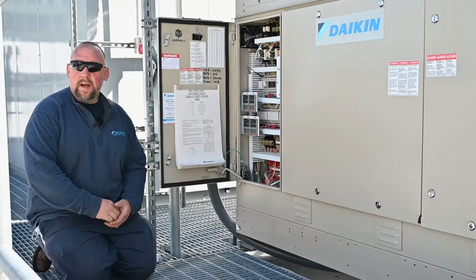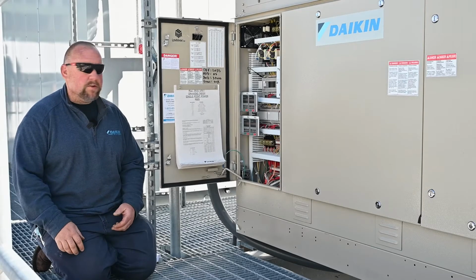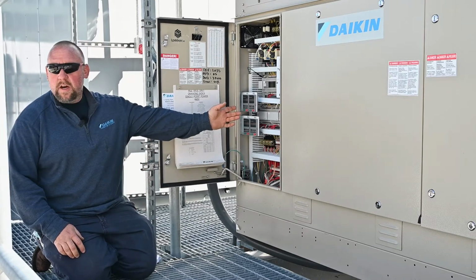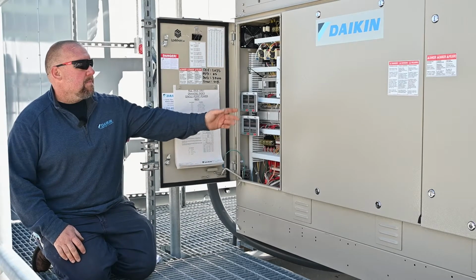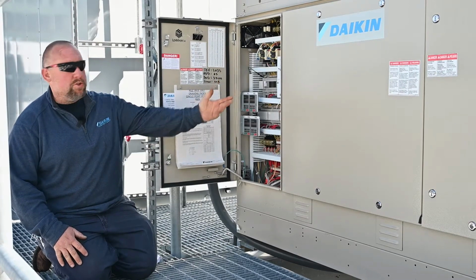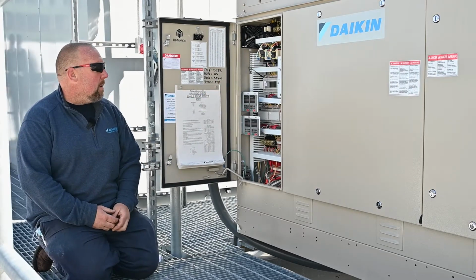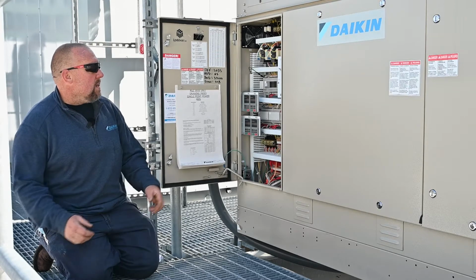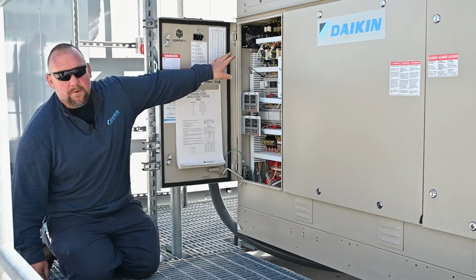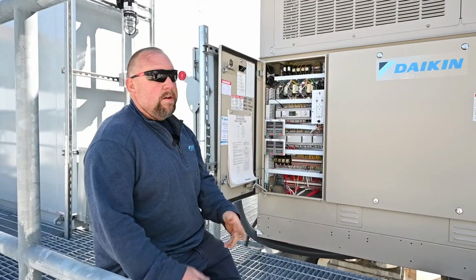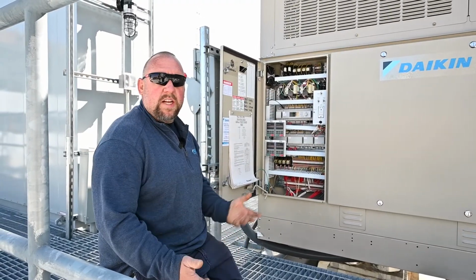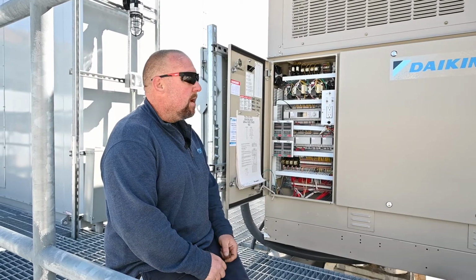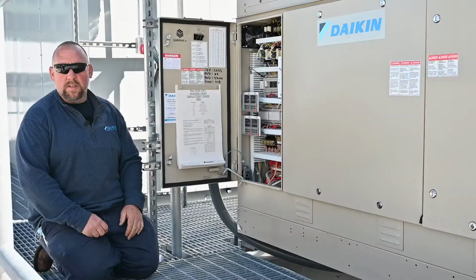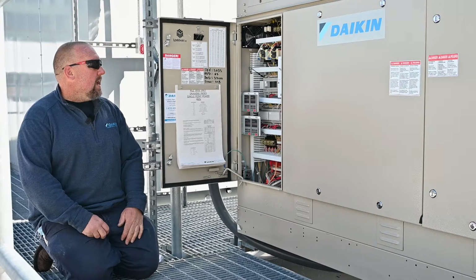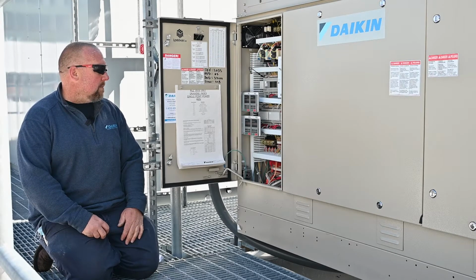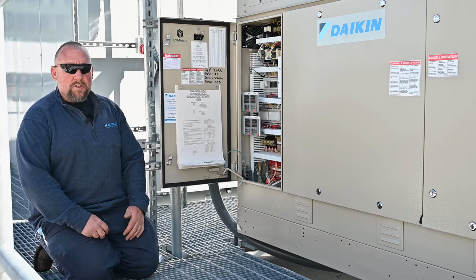All right, again, my name's Sean. I'm with Daikin Applied. We just moved over to the other side of the unit. As you can see, the unit controller is right in here. You have your on-off switches. You shouldn't really ever have to mess with any of that. You have a small fan up here for a high ambient. The only thing you can check with that is to make sure it's not blocked with any leaves or anything. It keeps everything cool inside, draws air through. Anything else with the maintenance, there isn't so much to do.